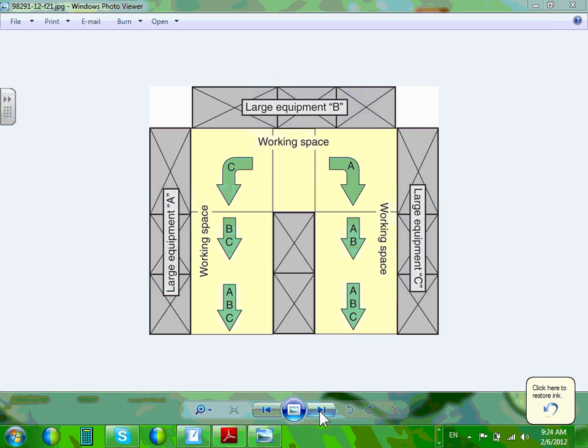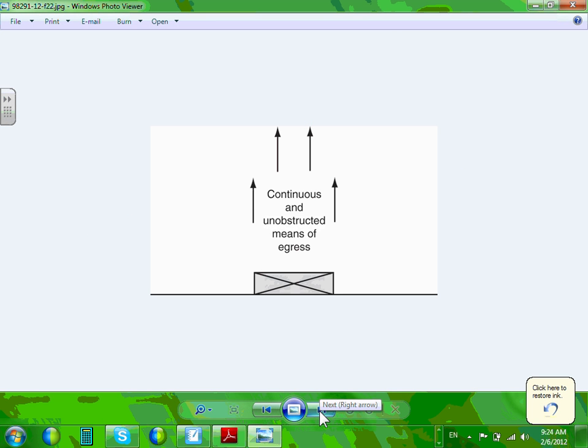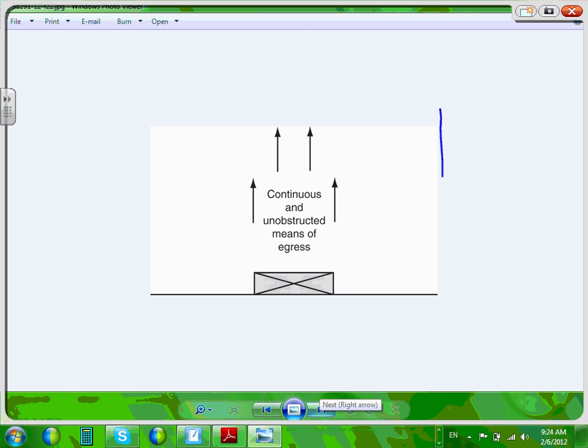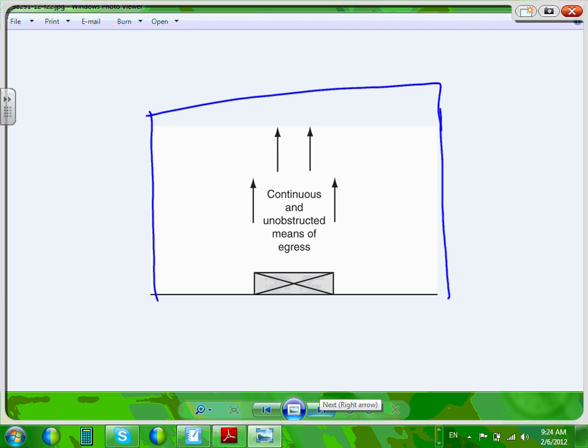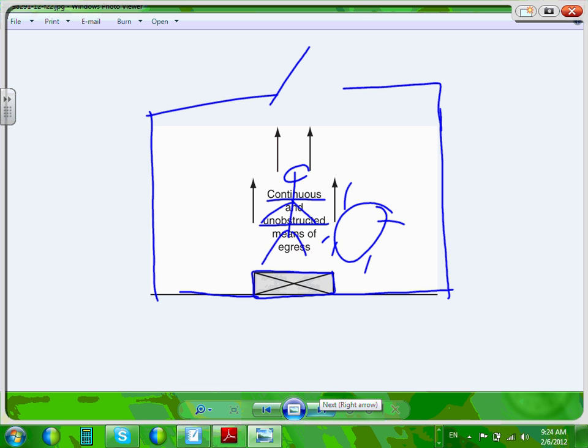I'm going to spare you the high voltage section. Or, here's another alternative for you. Here's a room, and here's my one entrance coming into the room. The alternative, my friends, is you have unobstructed, they call it continuous unobstructed means of egress. Look at how we place our switch gear here. If there's a big ball of fire coming out of here, and your friend Chad is working on the equipment, he can get out of there, one-way direction, unobstructed, straightforward. Then you don't have to have another entrance.